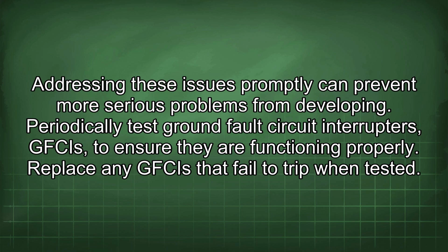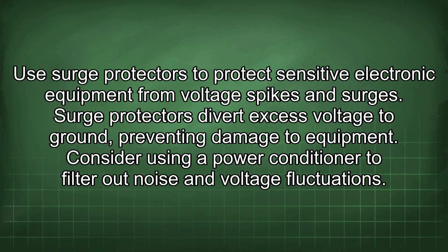Periodically test ground fault circuit interrupters, GFCIs, to ensure they are functioning properly. Replace any GFCIs that fail to trip when tested. Use surge protectors to protect sensitive electronic equipment from voltage spikes and surges. Surge protectors divert excess voltage to ground, preventing damage to equipment.